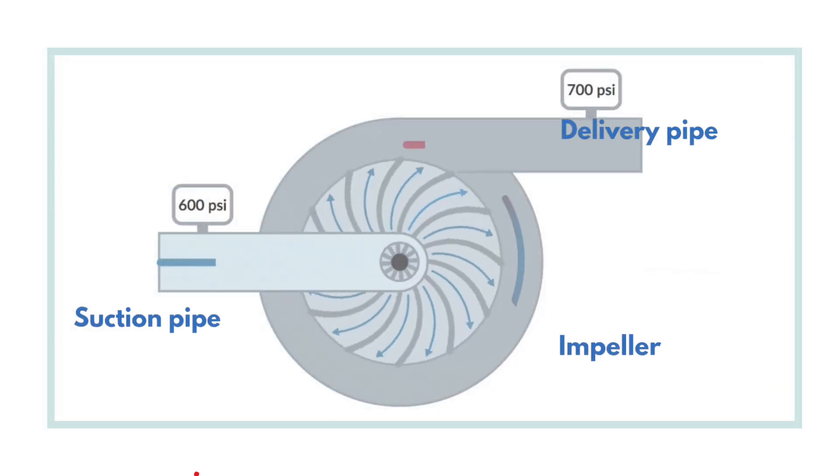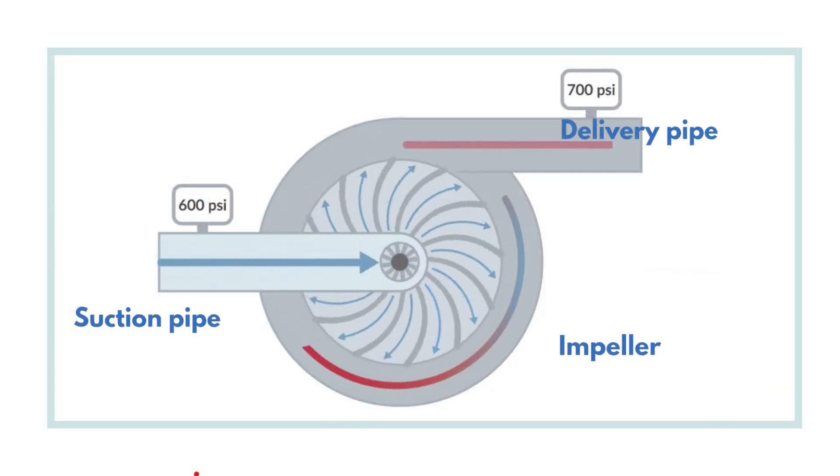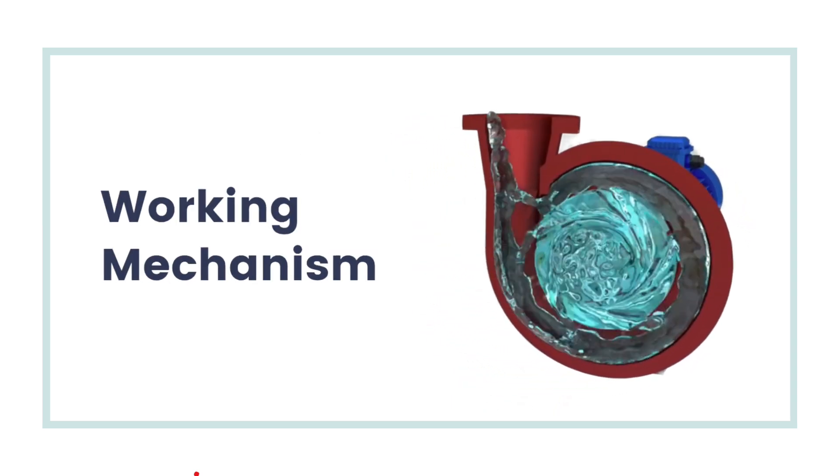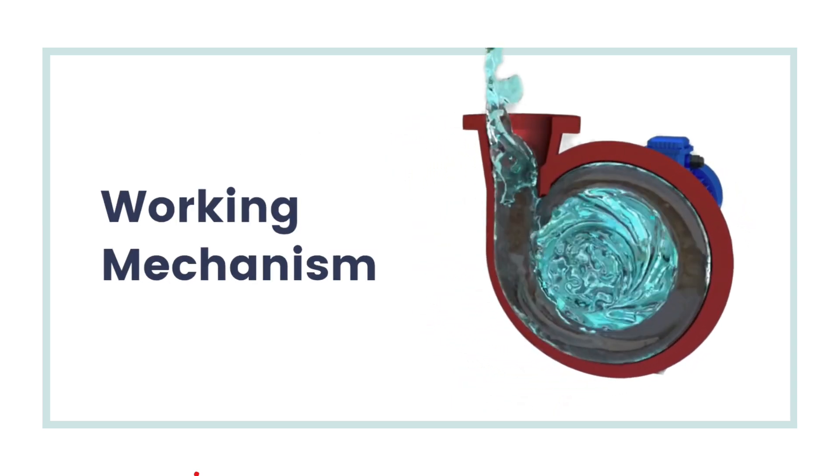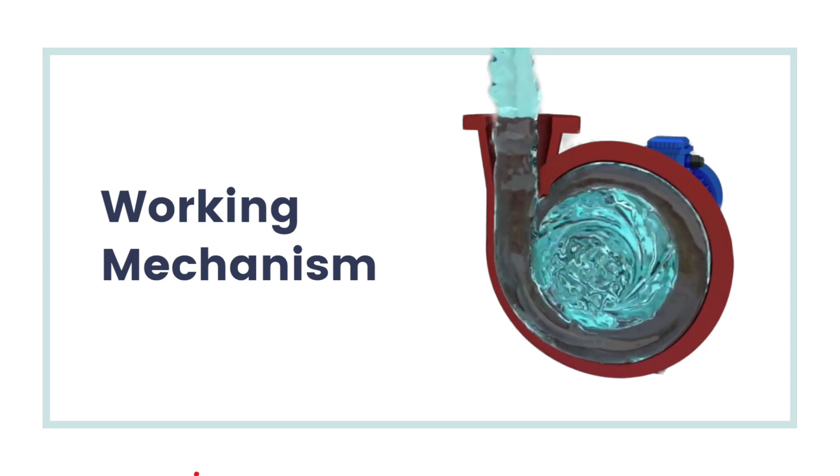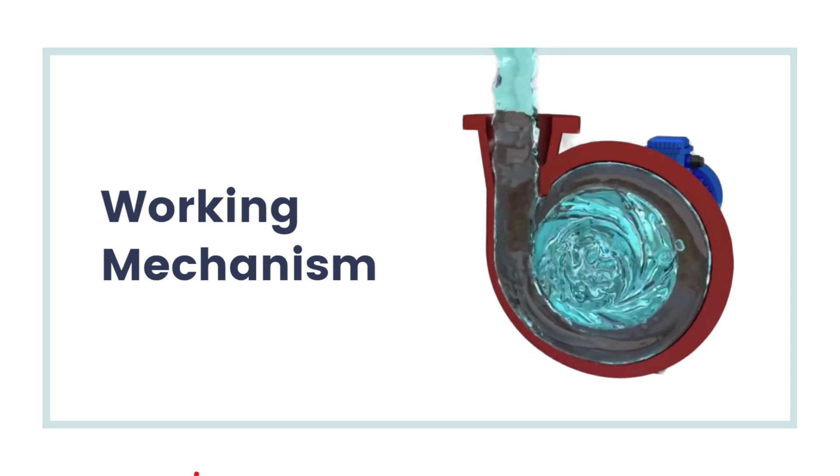Now if I talk about the working mechanism: fluid enters through the suction pipe and reaches the eye center of the impeller. The impeller rotates, driven by the motor, and imparts kinetic energy to the fluid as the fluid moves outward due to centrifugal force.